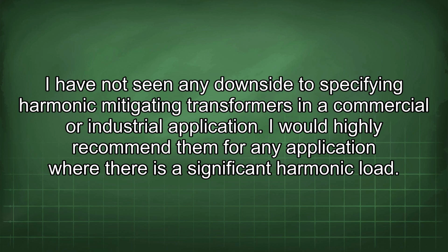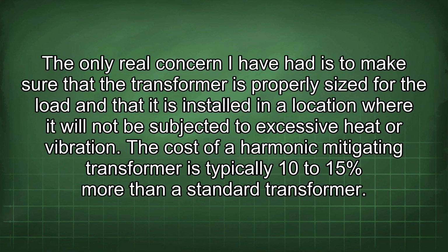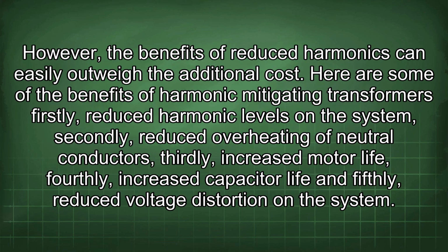I would highly recommend them for any application where there is a significant harmonic load. The only real concern I have had is to make sure that the transformer is properly sized for the load and that it is installed in a location where it will not be subjected to excessive heat or vibration. The cost of a harmonic mitigating transformer is typically 10 to 15% more than a standard transformer. However, the benefits of reduced harmonics can easily outweigh the additional cost.